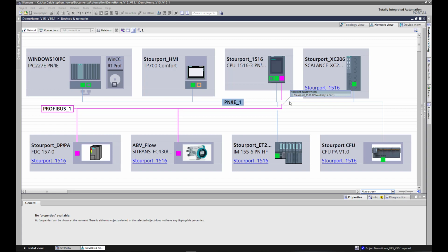and it has to sit on the Profinet network. Now if you haven't got Profinet on your site, don't panic, because what you can do is you can buy something called an IE/PB link that will connect one side to your DP network, and then the other side has an industrial Ethernet, inverted commas, Profinet connection that will go to your PDM maintenance station box. So as long as we can get to either green or purple on your network, green is easier. We don't need any additional hardware. If you go to the purple Profibus DP, then some additional hardware may be required.